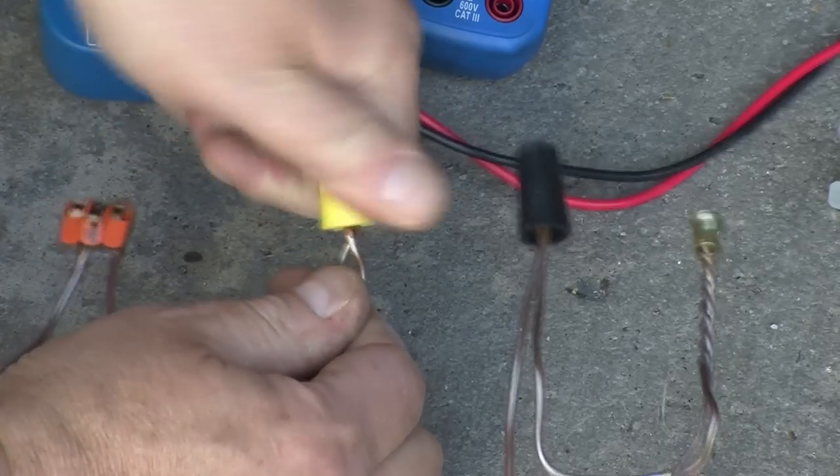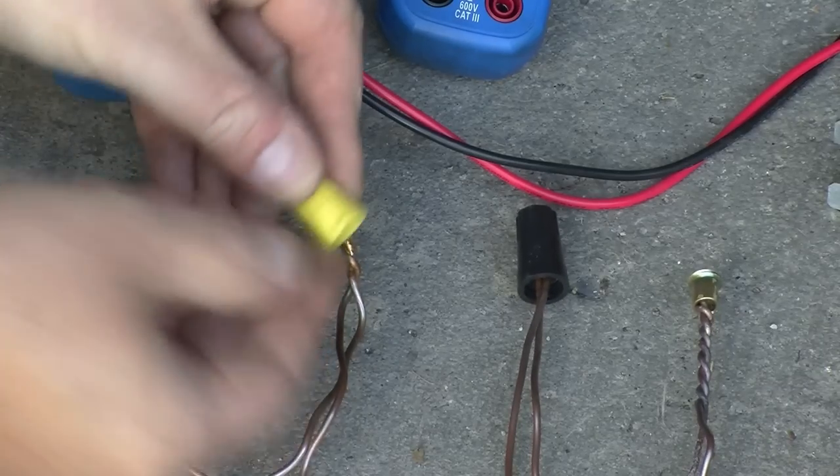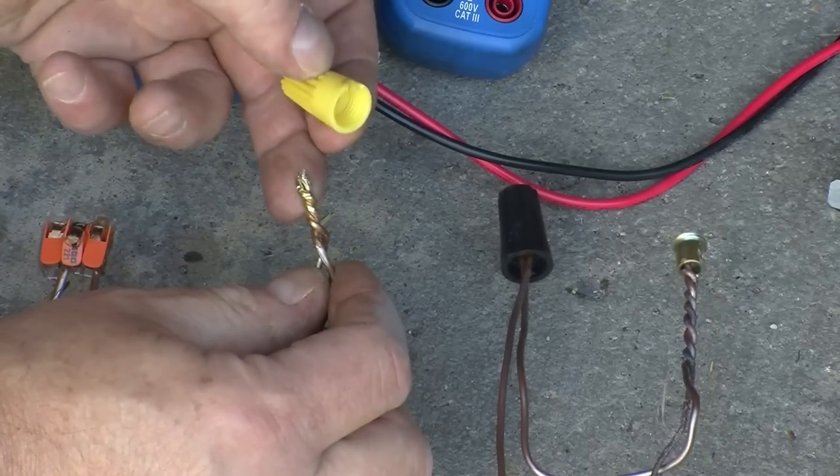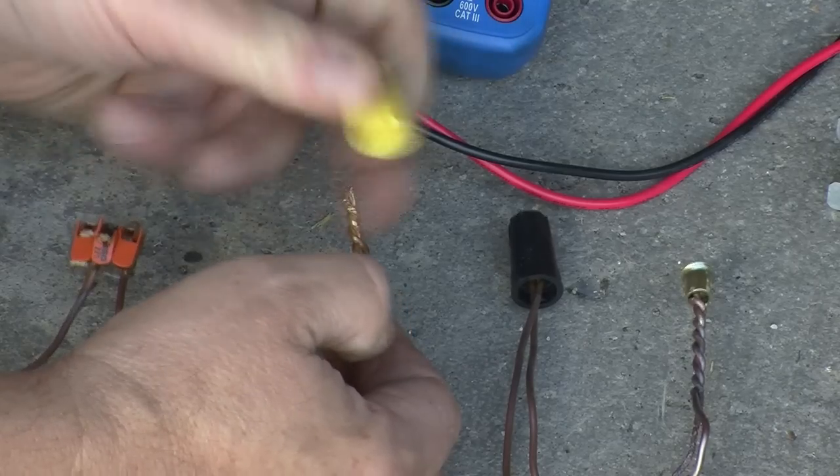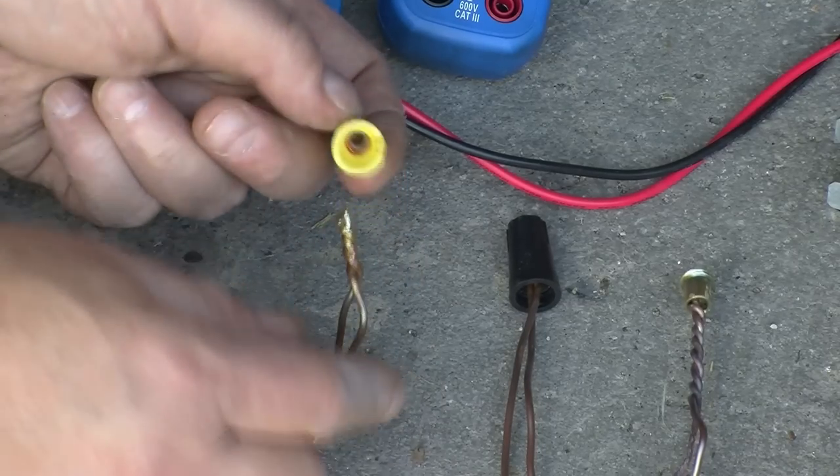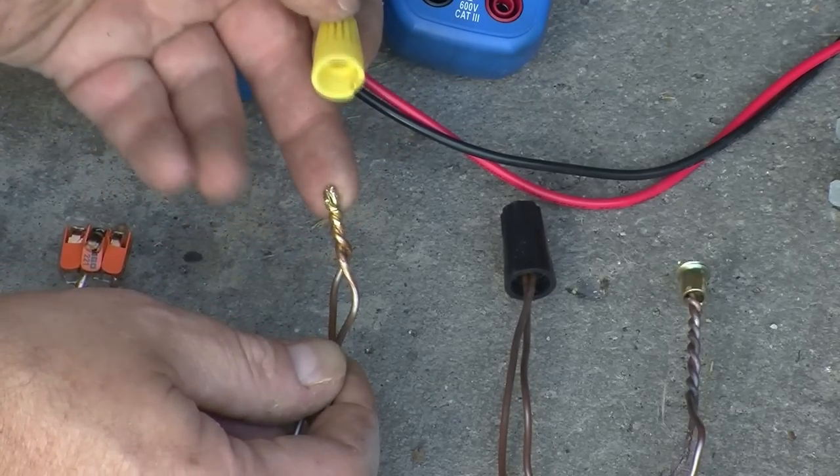What we should do is inspect the MAR connector and the wire nut, since they are the two most successful survivors. The wire nut or plain old MAR connector. There's certainly a bit of melting here. The connection survived pretty well. The wire is reasonably clean. The wire springy thing inside here seems to have survived very well. So that's very impressive.